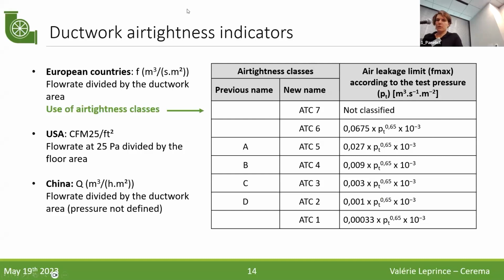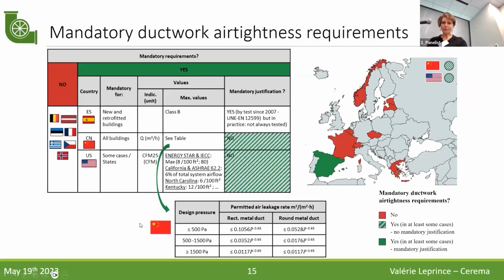In Europe we test according to airtightness class. There used to be class A, B, C, D for airtightness, with D being the best and A the worst. A few years ago this changed to airtightness classes 1 to 7, but they're the other way around, which mixes everyone up. In the US they use a unit of cubic feet per minute per square foot at 25 Pascal, and in China it's simply the flow rate divided by the area of the ductwork.